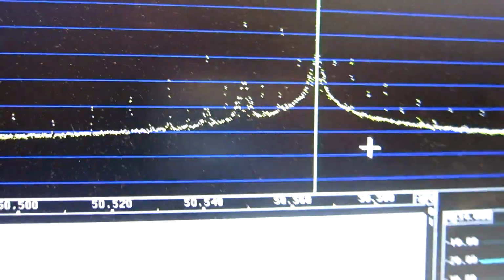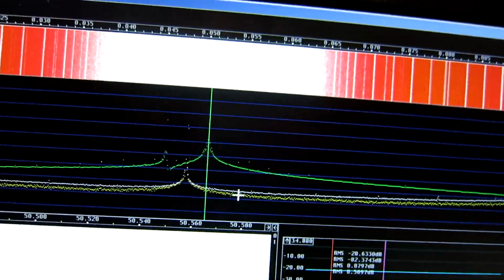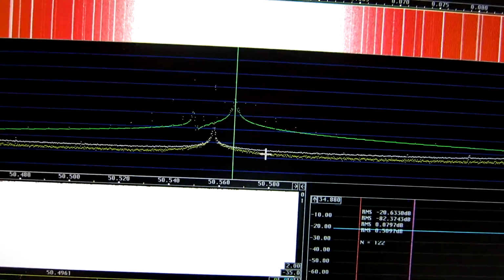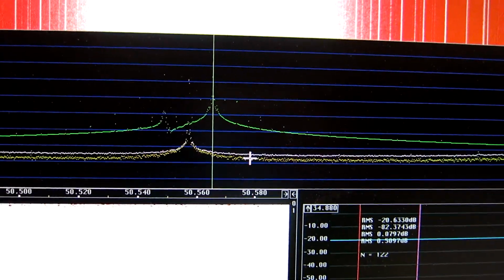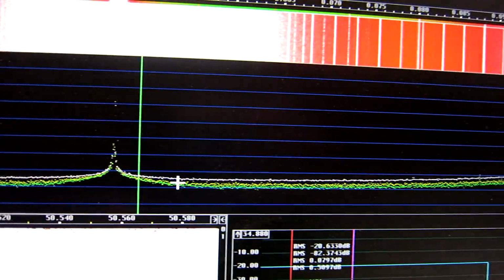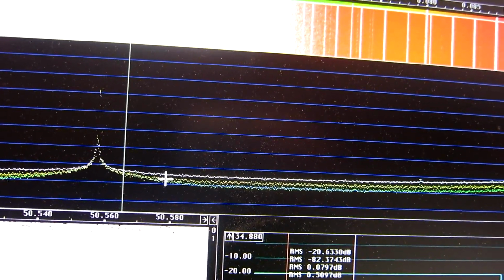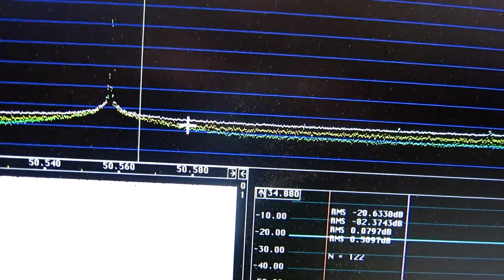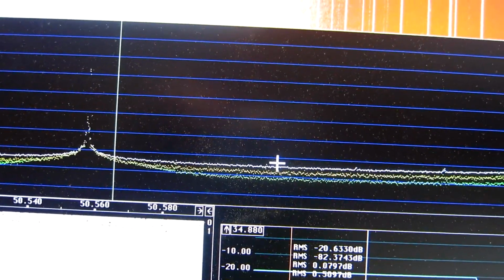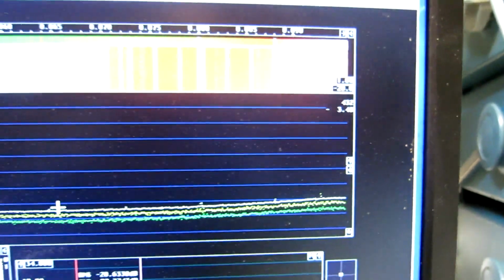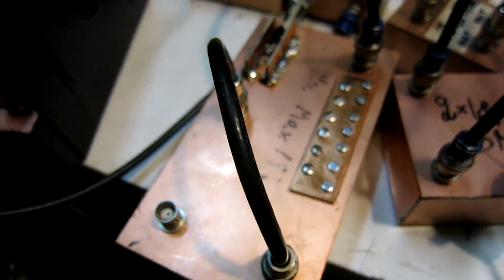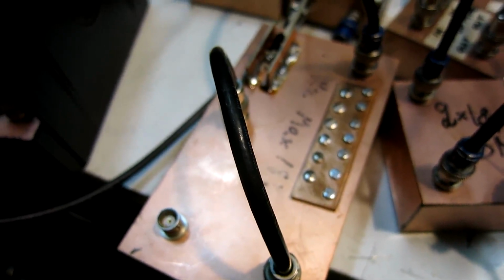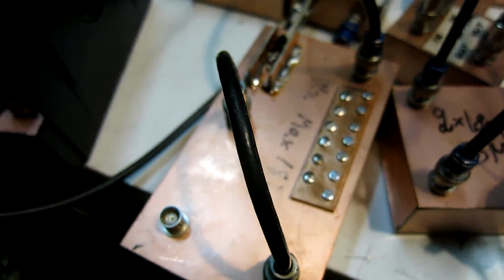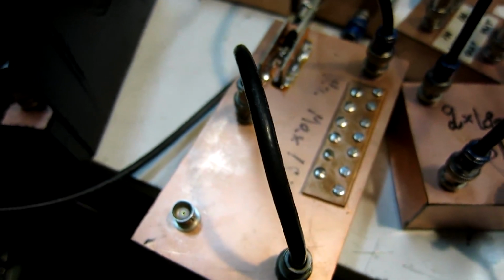Now I switch off this generator. So it's only the two 10 megahertz signals, and I clear the correlation spectrum. It takes some time for the averaging to take place, and it's clear that the green spectrum is well below the yellow, and the green is now from 350 averages, and I will wait for a while. I have had some stability problems with this box. It misbehaves if the voltage is too high or too low, and the range where it is okay is very narrow and depends on the temperature, so that's very impractical.